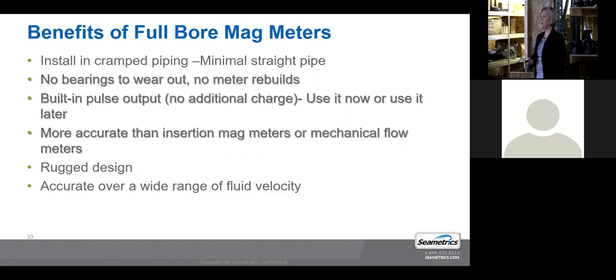With mag meters, you remove that element of moving parts. So as long as you have a full pipe of water, they'll start reading right away, at very, very low flow. And they'll read up to extremely high flow rates for that same reason. There's no moving parts in them. So they're accurate over a wide range of fluid velocity, which is another advantage of them.